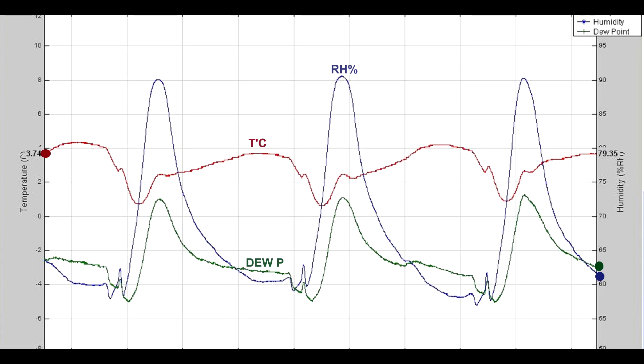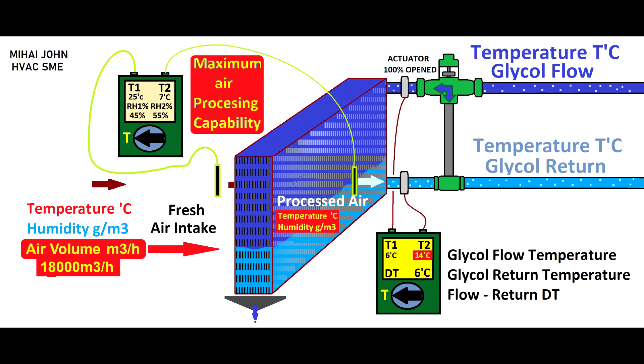Watching this trend, you will observe immediately that there is something wrong. The probe which reads the temperature and the humidity is instructing the PLC to act onto the actuators too late because of its location. That's an incorrect location. And then the heat exchangers do their job but too late, and then they overshoot. That's why you have sometimes too high humidity and then sometimes humidity is too low, and the temperature looks like that. So please watch my other video. I'm going to talk about the heat exchangers, the maximum air processing capability, and some other things that might help you to understand why your air handling unit is not working as it should. And you will learn how to analyze an air handling unit and then to overcome the mistakes done by some designers. Thank you.